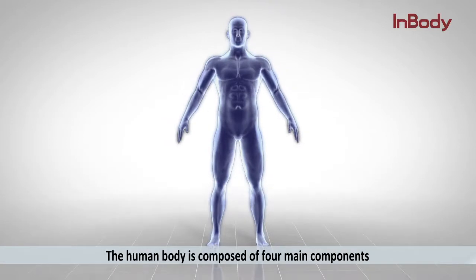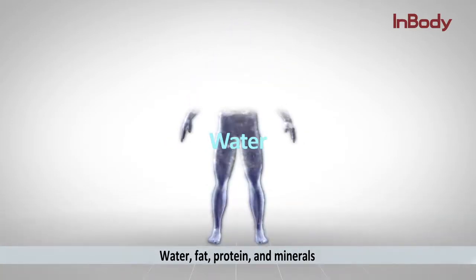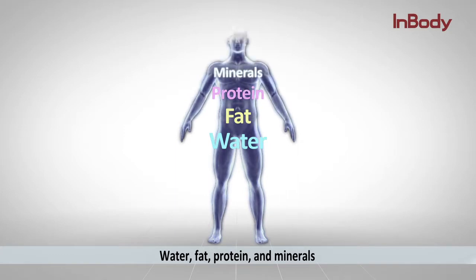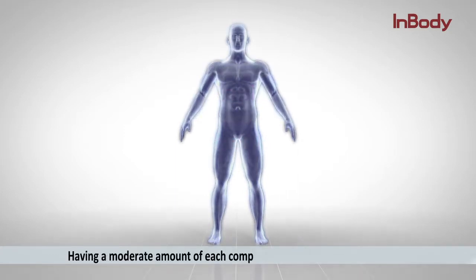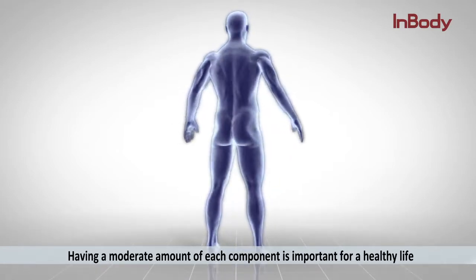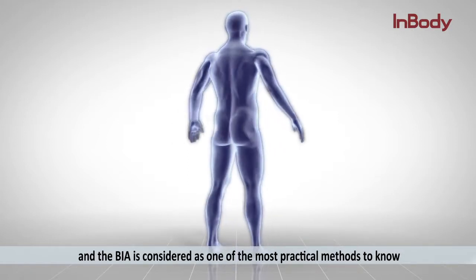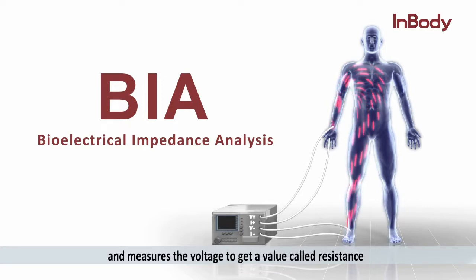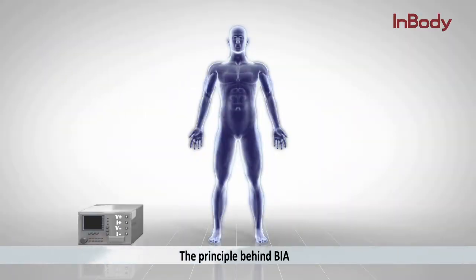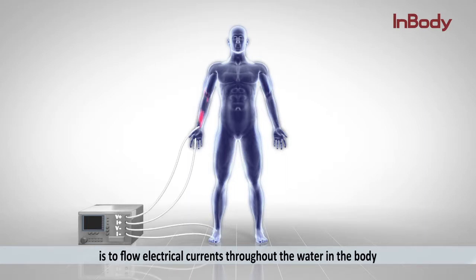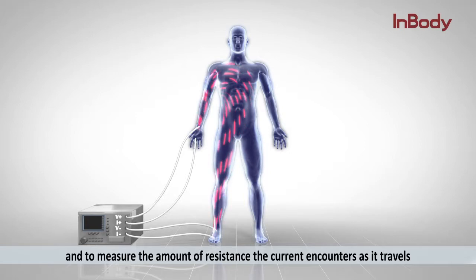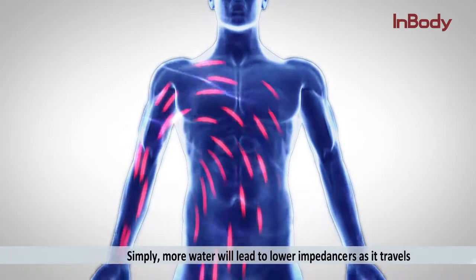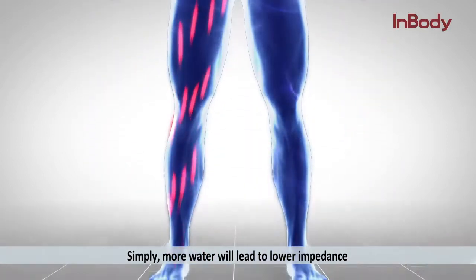The human body is composed of four main components: water, fat, protein, and minerals. Having a moderate amount of each component is important for a healthy life. BIA — Bioelectrical Impedance Analysis — is considered one of the most practical methods to assess body composition. This method applies small currents throughout the body and measures the voltage to get a value called resistance, also known as impedance. The principle behind BIA is to flow electrical currents through the water in the body and measure the amount of resistance the current encounters — simply put, more water leads to lower impedance.